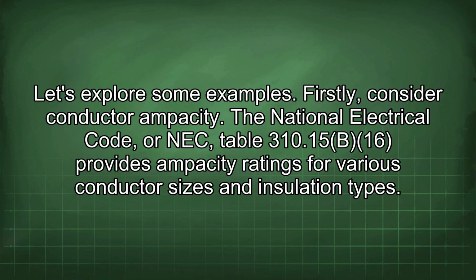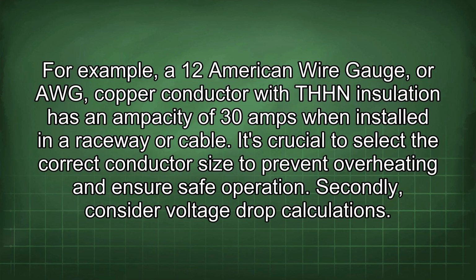The National Electrical Code, or NEC, Table 310.15(B)(16) provides ampacity ratings for various conductor sizes and insulation types. For example, a 12 American wire gauge, or AWG, copper conductor with THHN insulation has an ampacity of 30 amps when installed in a raceway or cable. It's crucial to select the correct conductor size to prevent overheating and ensure safe operation.